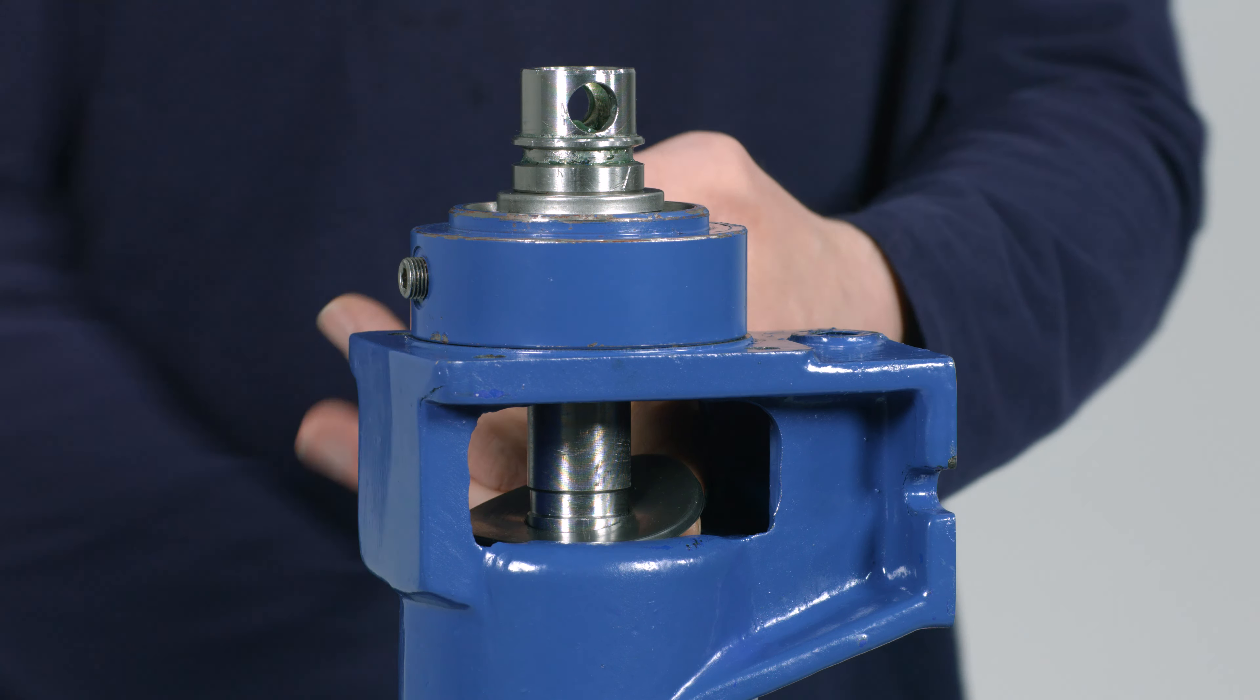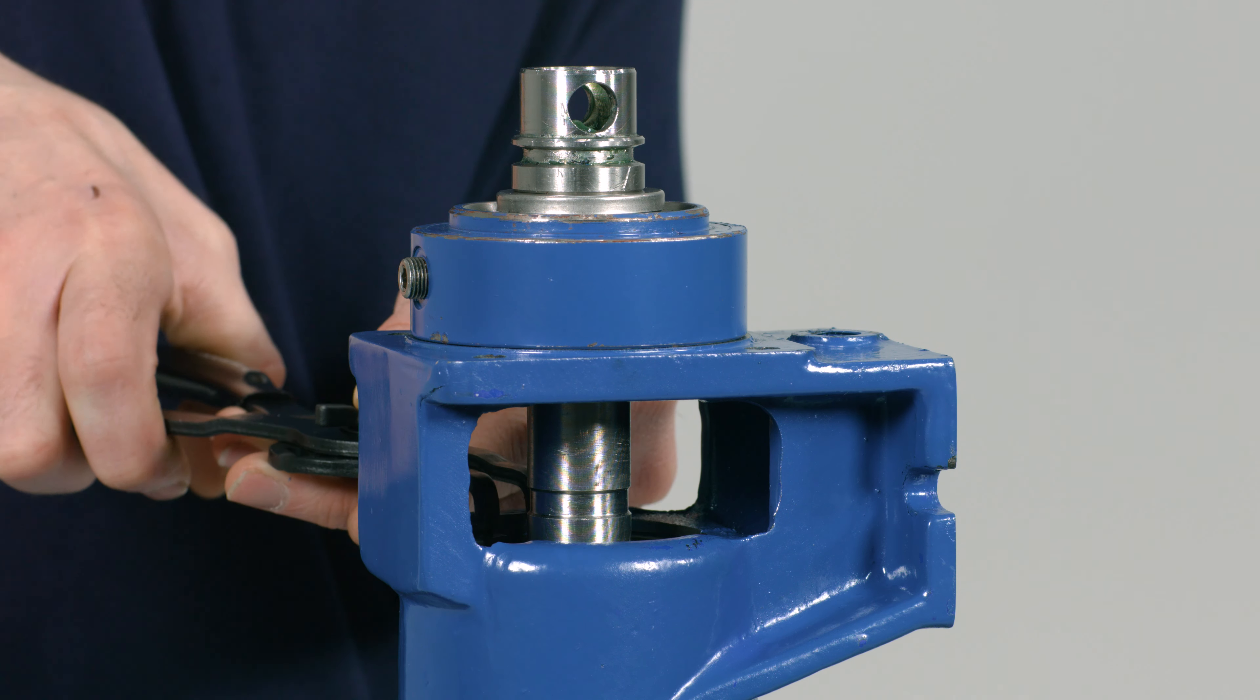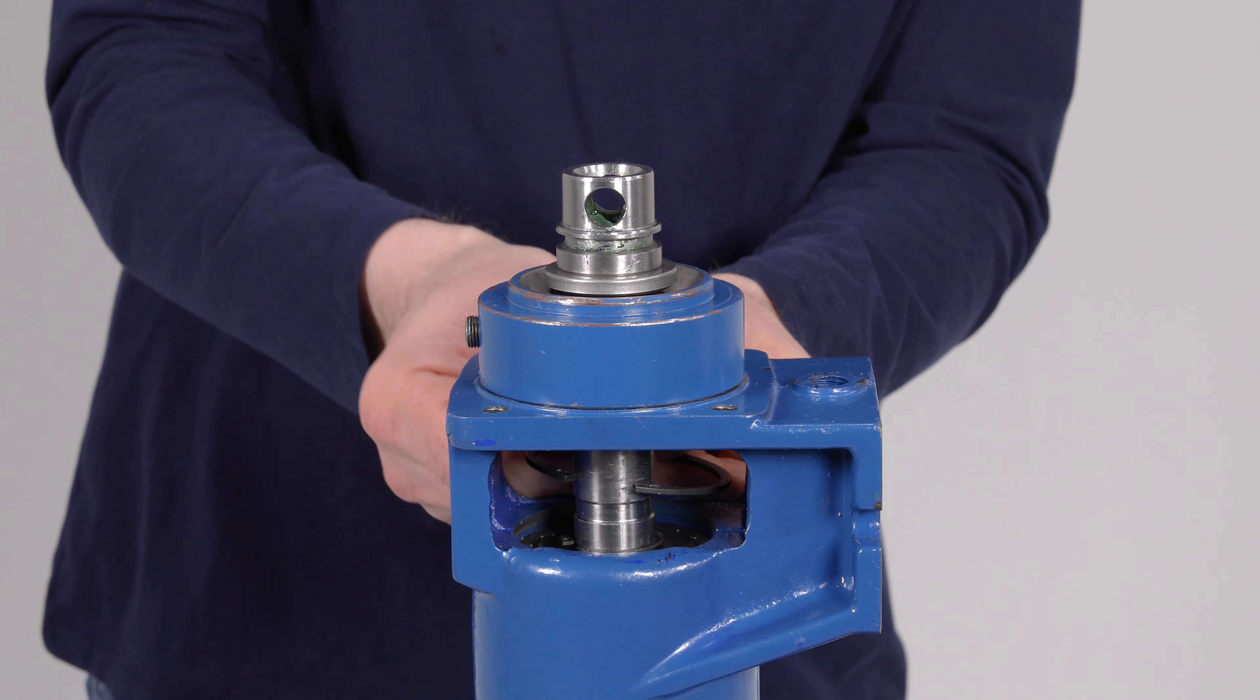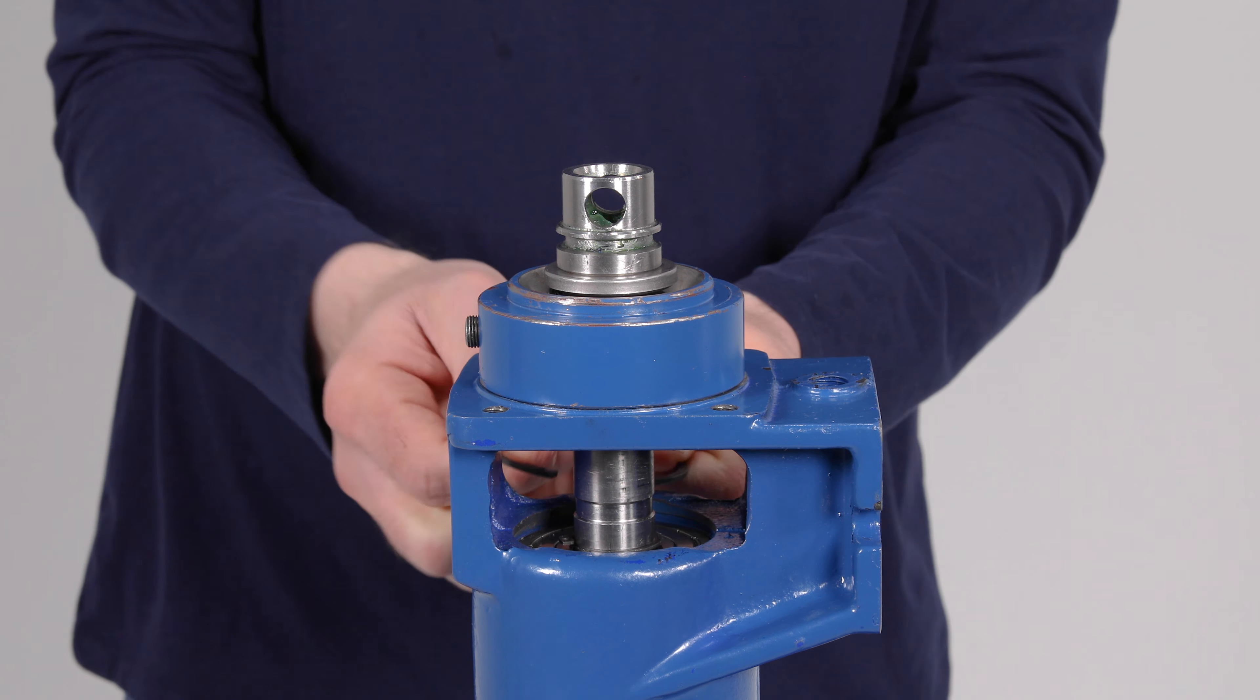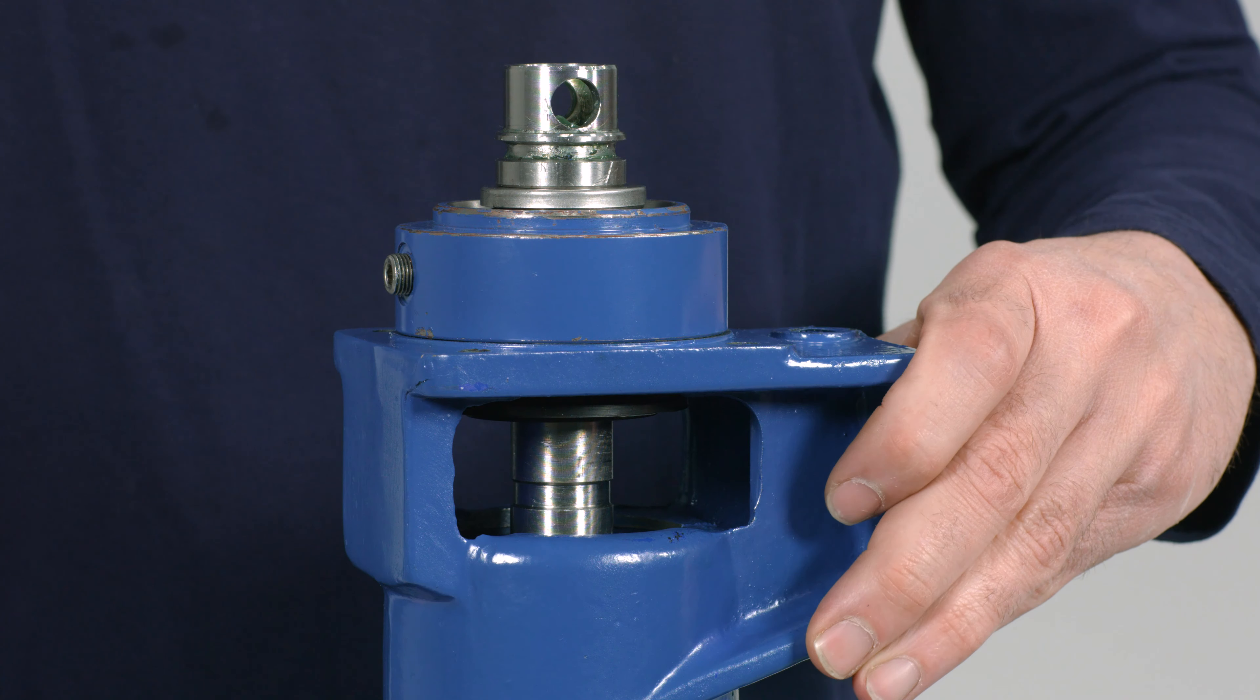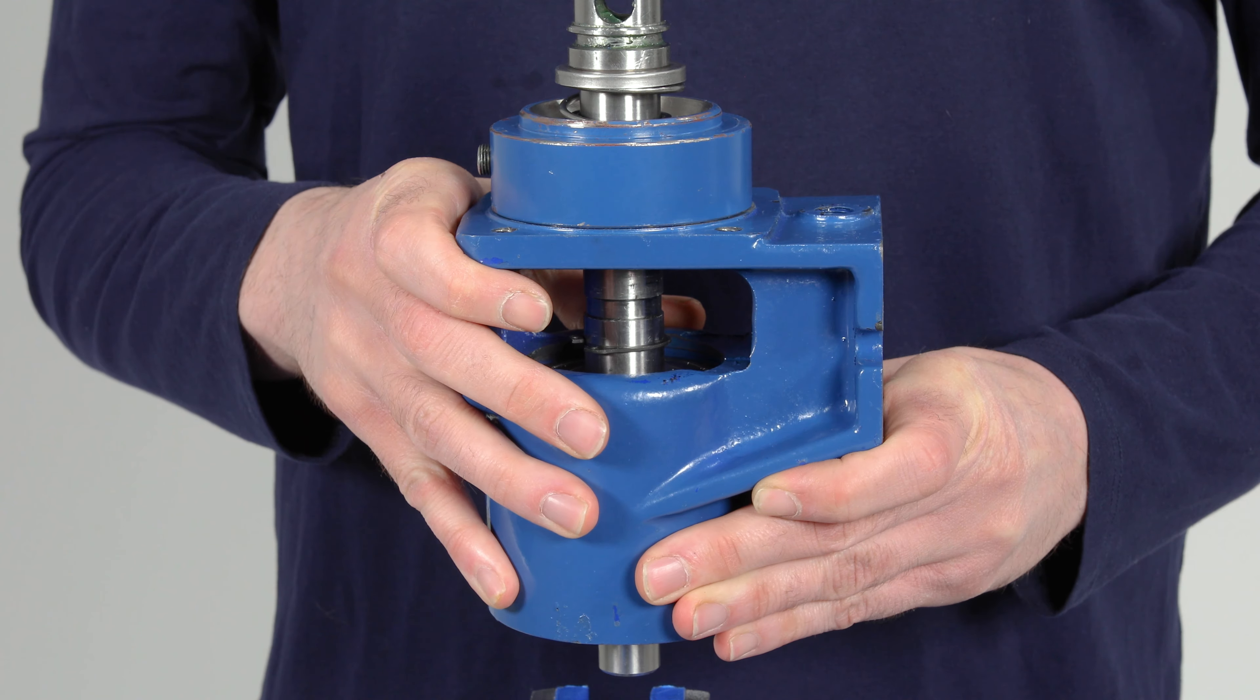Slide the flinger ring up against the top bearing. Using a pair of snap ring pliers, remove the snap ring from inside the bearing housing. Place the bearing housing in a press with the keyway facing up. Press the drive shaft until the bearing and spacer come loose from the bearing housing. Remove the bearing housing and drive shaft from the press and place on a workbench.